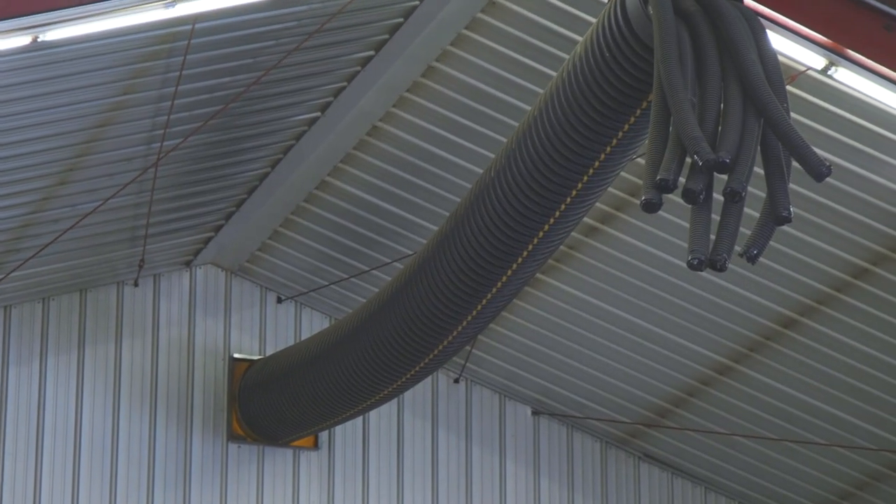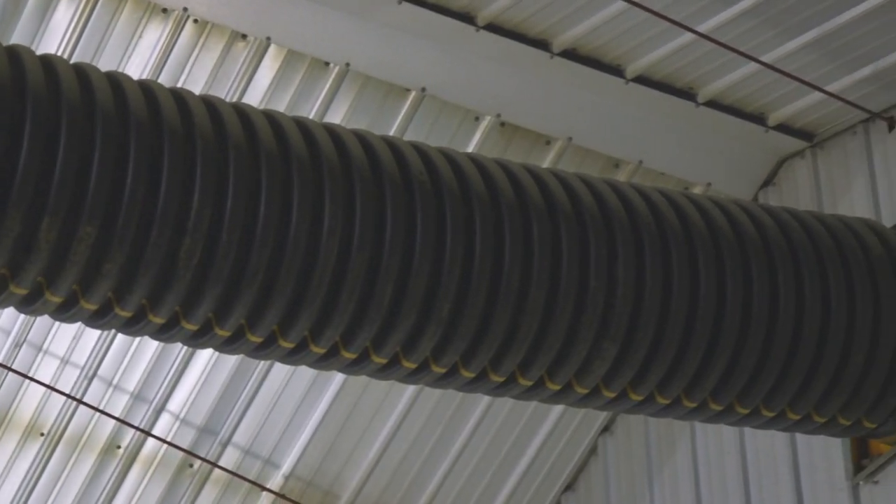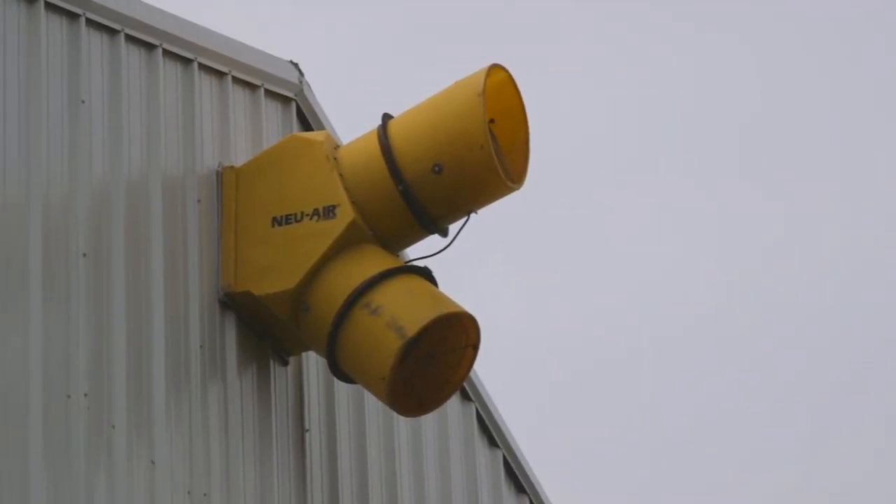You have another addition that's very unique — your ventilation system, which is almost like spaghetti work of tubes coming off the ceiling. You've got to explain this to me. It's a system to allow the dirty air to go out over tubes and recapture some of the heat in the winter. You can't just have an exhaust fan — you need an inlet also, otherwise you just pressurize or vacuum the building and there's no exchange of air. So this system has small tubes that come in and come down to about four feet above the floor level, down the walls, letting clean air in with a fan blowing it in, and then a fan that sucks the dirty air out over those tubes up in the ceiling.